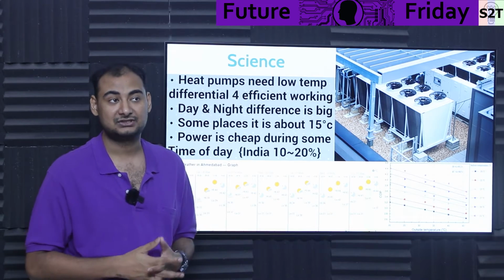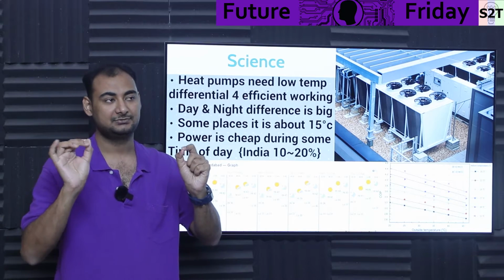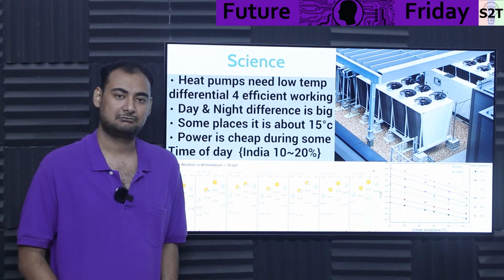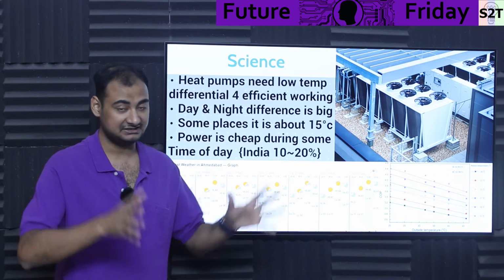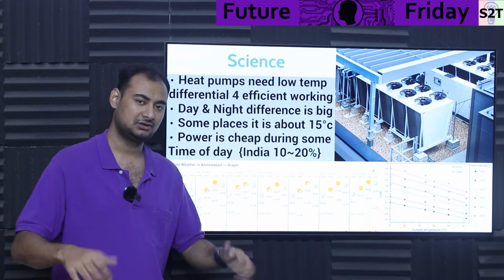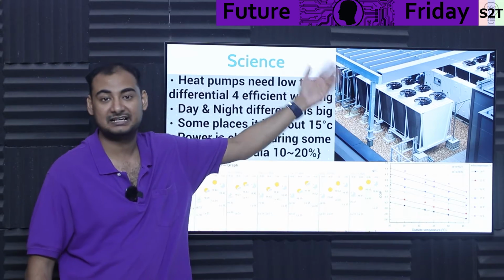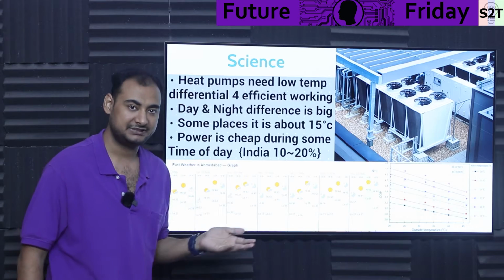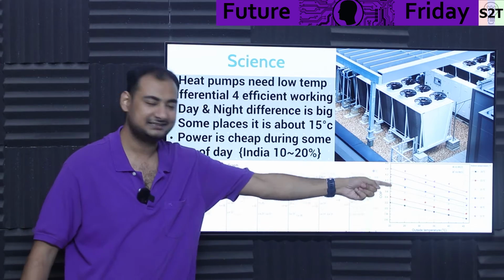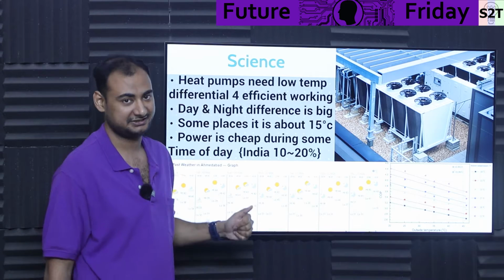For us, it translates to a scenario where from 12 noon to around, let's say, 2 p.m., it's so hot that our AC compressor is going, but the cooling is like, it does not cool. Same AC, same house, same day, at evening time, I turn it on, and half an hour later it's like, chill bro, I got this. How the heck? Again, outside temperature. Outside temperature affects this puppy, that affects the compressor's ability to dump heat. And that's why the ton rating, the BTU rating, is lol. Unless the company gives you a graph like this, you do not know what the cooling power is. And again, humidity also has to be there, but that became too complicated.